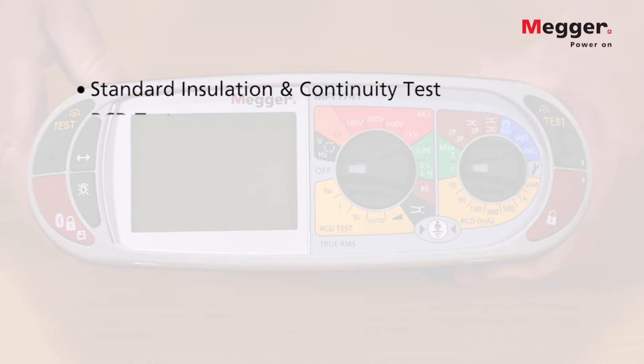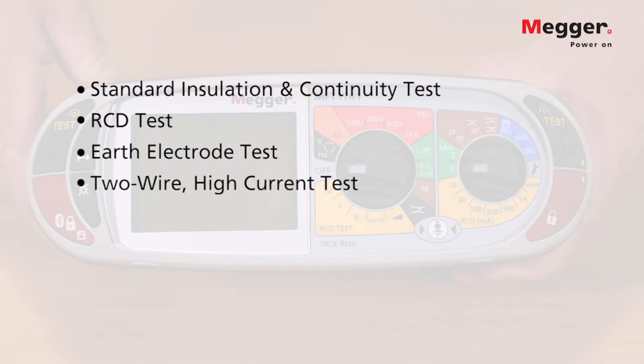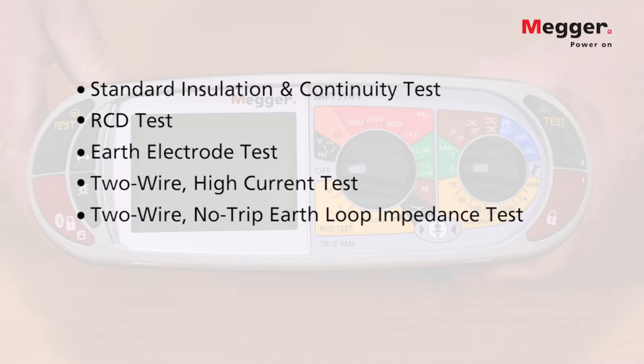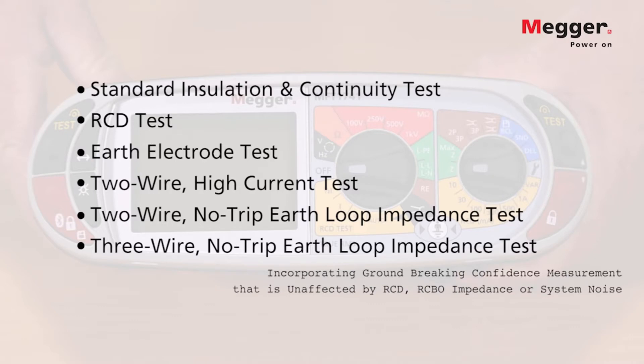In this presentation we will run through the ranges and features of the Megger MFT 1741 Multifunction Tester. Like the rest of the range, the 1741 includes a standard insulation and continuity tester, an RCD tester, a full earth electrode tester, and a two wire high current and two wire no trip earth loop impedance test. In addition, we have a patented three wire no trip earth loop impedance test which incorporates a groundbreaking confidence measurement that is not affected by RCD or RCBO impedance or system noise.